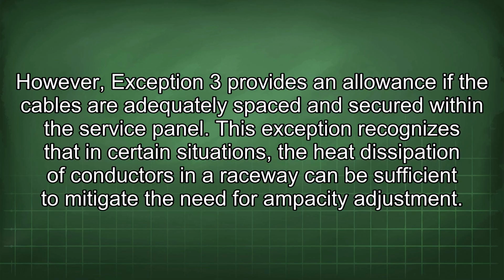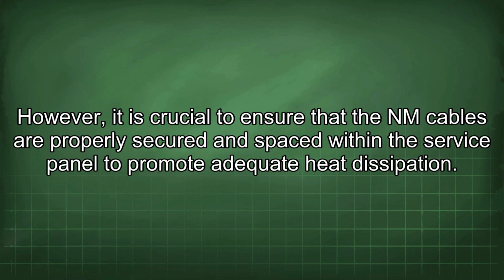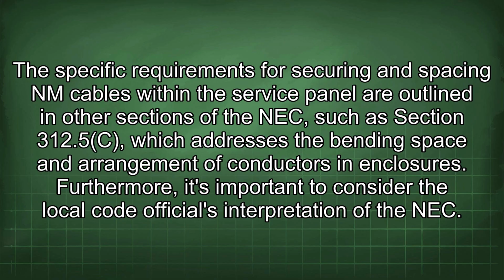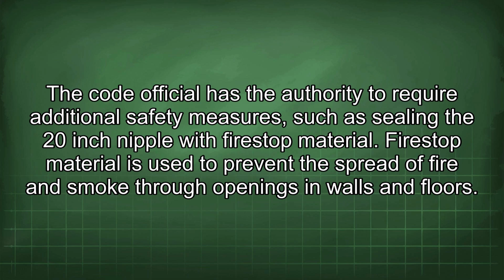This exception recognizes that in certain situations, the heat dissipation of conductors in a raceway can be sufficient to mitigate the need for ampacity adjustment. However, it is crucial to ensure that the NM cables are properly secured and spaced within the service panel to promote adequate heat dissipation. The specific requirements for securing and spacing NM cables within the service panel are outlined in other sections of the NEC, such as Section 312.5(C), which addresses the bending, space, and arrangement of conductors in enclosures. Furthermore, it's important to consider the local code official's interpretation of the NEC. The code official has the authority to require additional safety measures, such as sealing the 20-inch nipple with firestop material.